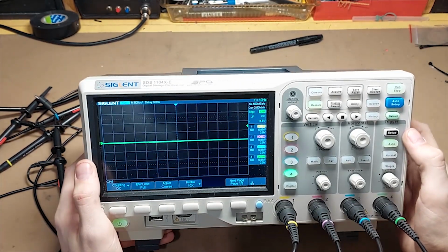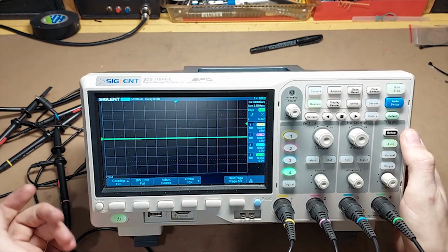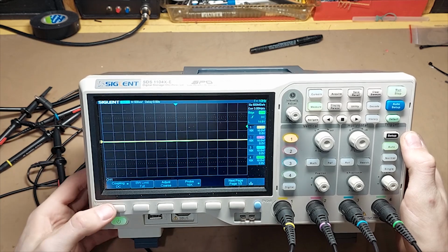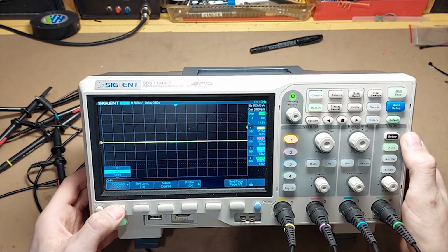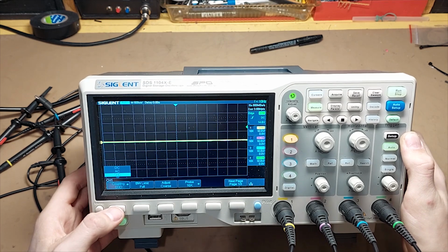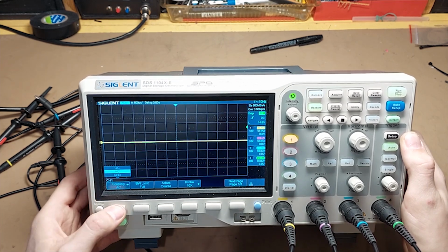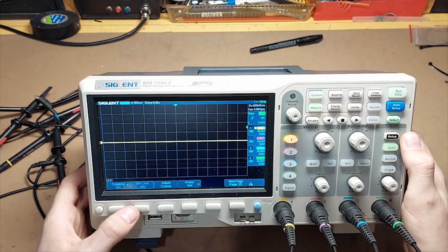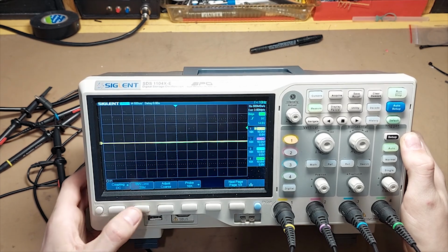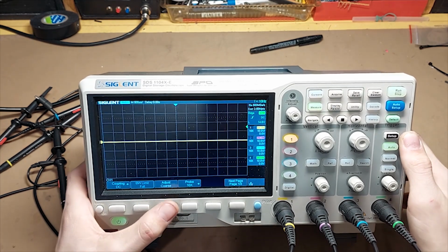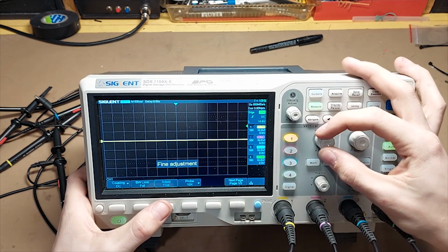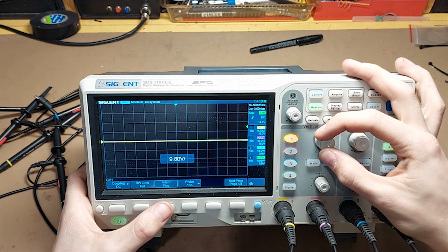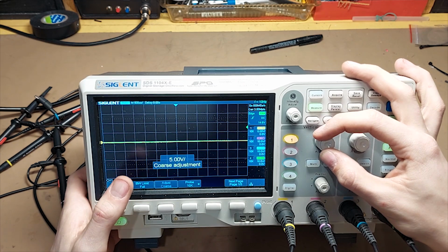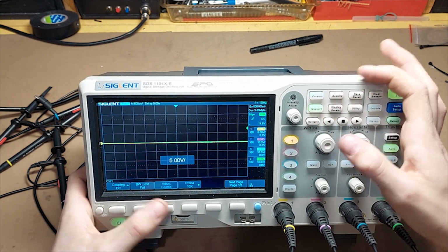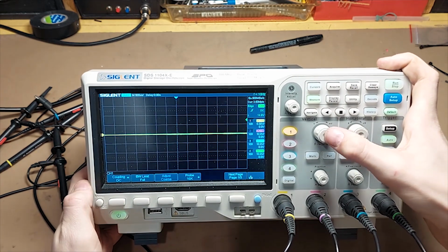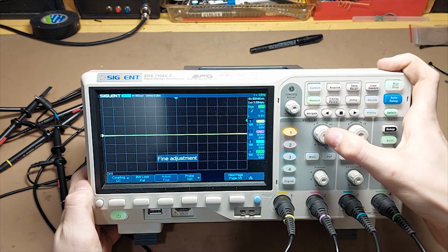So yeah, that's all probes set now. And here on the probe menu you can select the coupling. There's DC, AC, and ground, which basically just internally connects it to ground. So that's DC, AC, ground. Here you can set your bandwidth limit to 20 megahertz, enable or disable it. And this is the coarse and fine adjustment. So with fine adjustment you go in small steps, and in coarse, bigger steps. And you can also choose fine or coarse by pressing on the vertical adjustment knob.